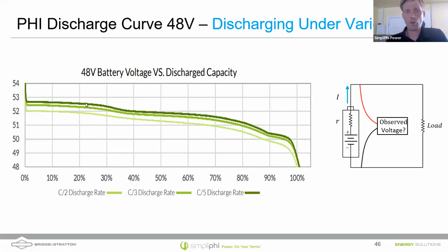As I increase the discharge rate, the curves shift downward. And if I'm at a C/2 discharge rate, I'm discharging very rapidly. I'm losing the most voltage across that resistor. And so typically it's on the order of a couple of volts. So I'll drop immediately from 54 down to 52 at a C/2 discharge rate. And at a 50% state of charge, I'm only about 51.4 volts, 51.3. So you notice that difference here. Just keep in mind that when you're looking at a voltage to determine the state of charge of a battery, it depends on how quickly that battery is charging or discharging.